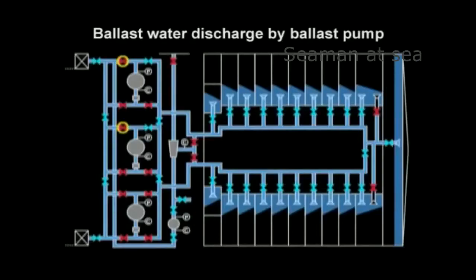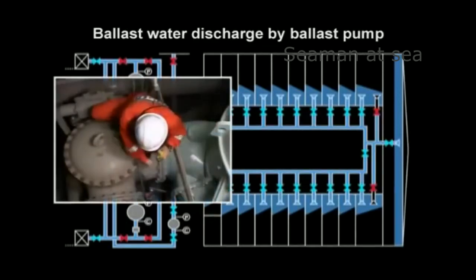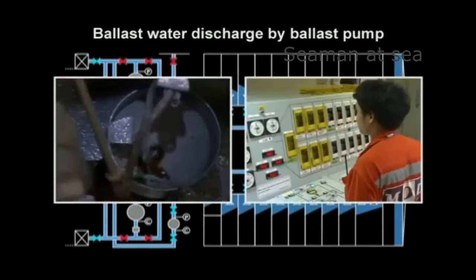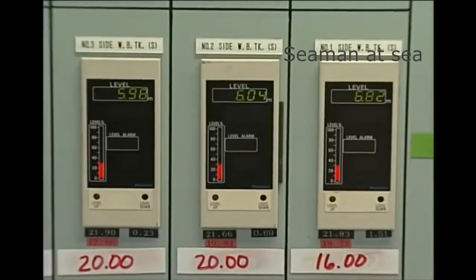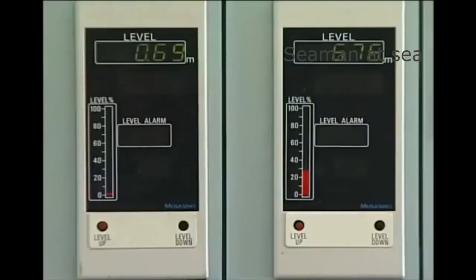Next, we'll proceed to ballast water discharge by ballast pump. The ballast pump starting procedures are the same as for filling. Make sure to conduct air purging from the pump and confirm the state of valves and gauges. Watch the water level since cavitation occurs as the level drops, which causes the water head pressure from the pump's suction valves to decline. As the water level drops further to approach the tank bottom, exercise precautions against air drawing. Watch the gauge carefully and readily respond to the risk of air drawing.